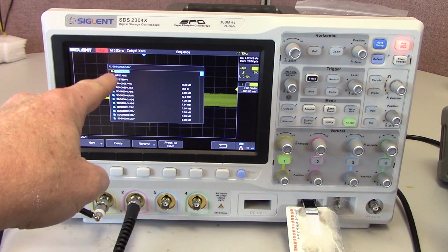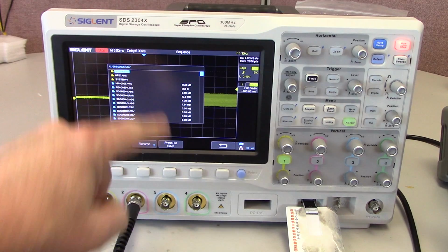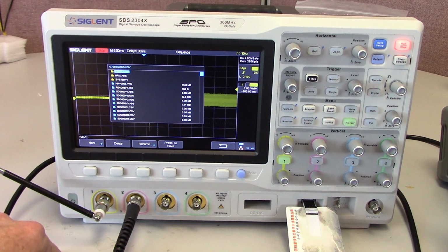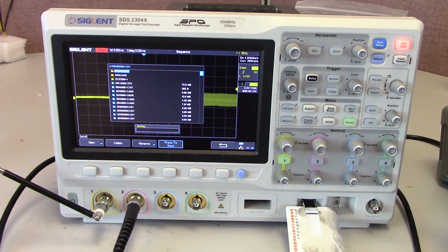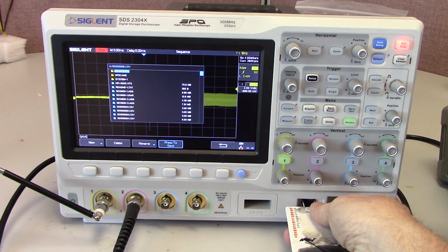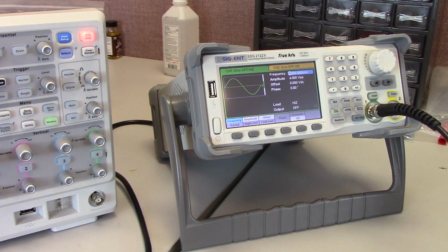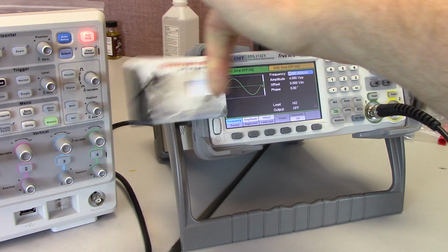And we can rename our file. Right now it's SDS200005 with the CSV type on there, and we'll just use that. So we'll press to save. Now that's going to convert that to a CSV format, and the file should be about 3 meg in size, and you can see it's saving it to the flash drive there. And now we're finished. Store data success. We'll unplug the flash drive and we'll jump over here to our generator, where we'll simply, you guessed it, plug that into the port of the generator where it is recognized.